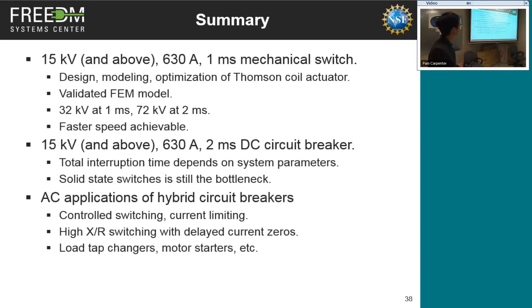We have designed, modeled, and optimized the Thomson coil for this mechanical switch, and validated our finite element model. We have achieved 32 kilovolts at 1 millisecond, 72 kilovolts at 2 milliseconds, and we can achieve faster speeds.